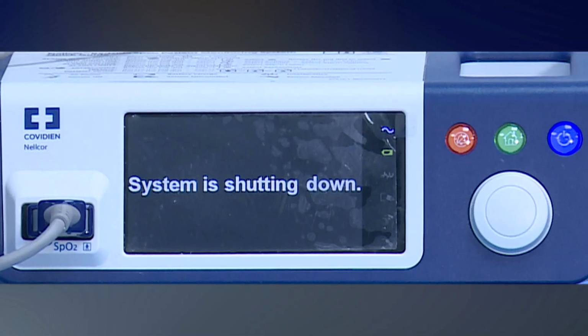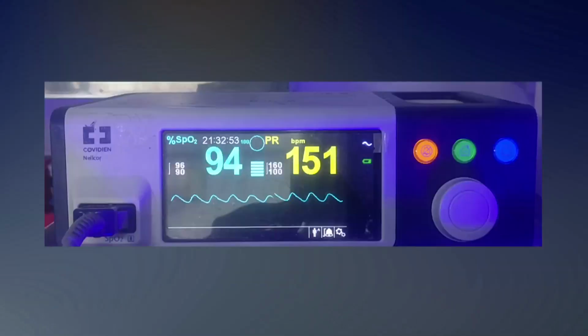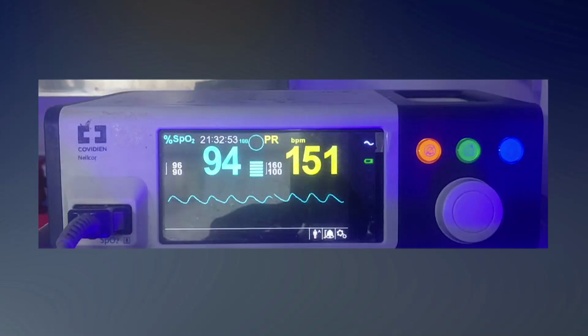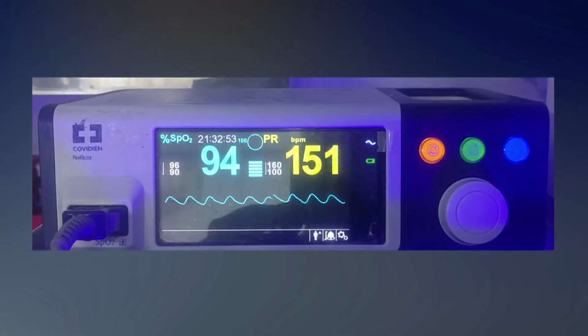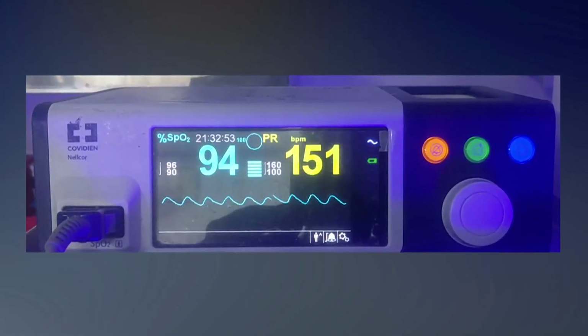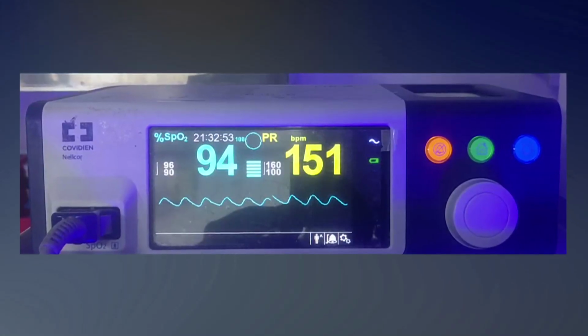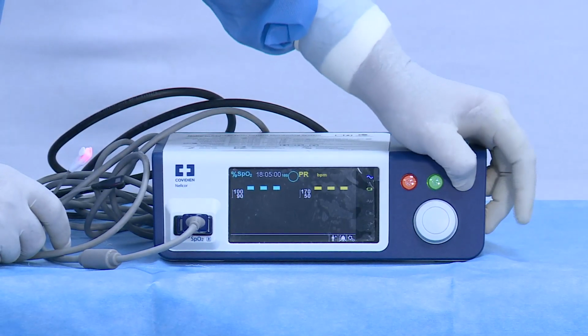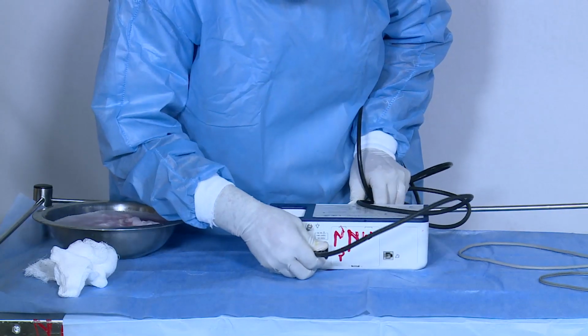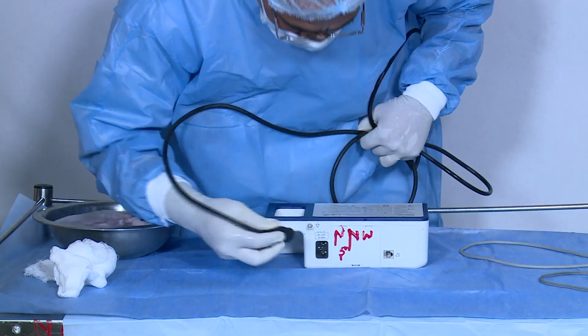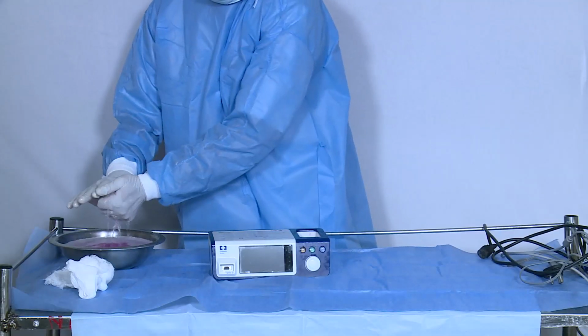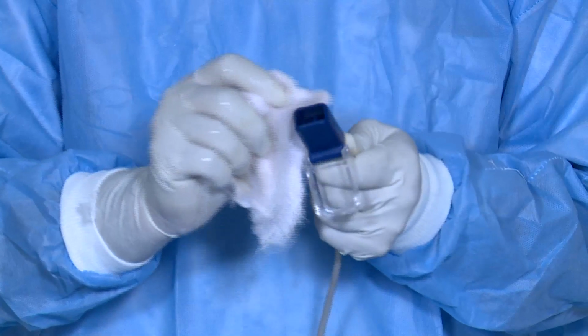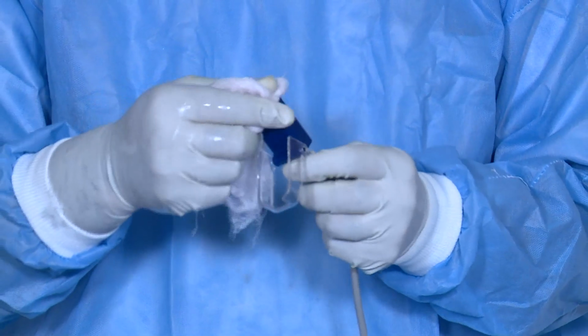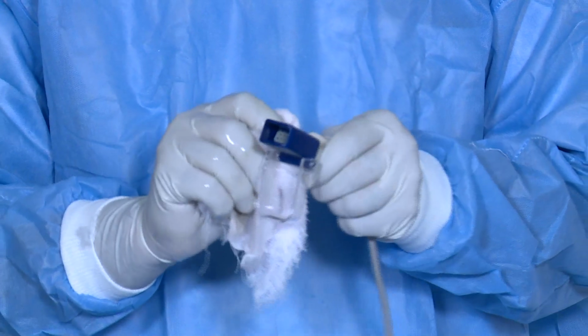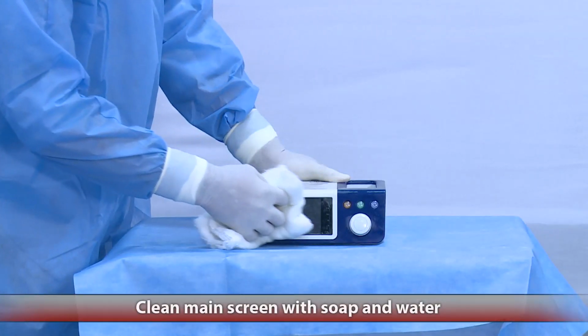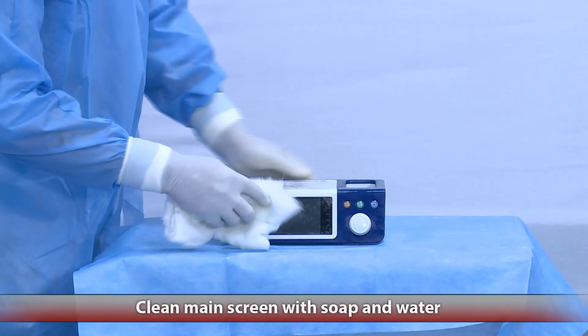Now, let us learn the cleaning of the pulse oximeter. All parts of the pulse oximeter come under high-touch surfaces and hence need thorough cleaning and disinfection. Always ensure that the pulse oximeter is turned off and the power cord is disconnected from the socket before cleaning. Wipe clean the power cord and the extension cable with a surface disinfectant containing glutaraldehyde. Clean the main screen using a cloth dipped in soap and water.